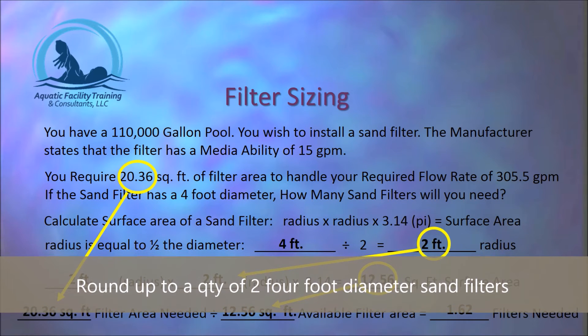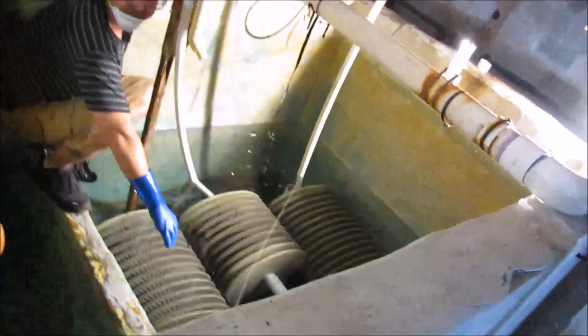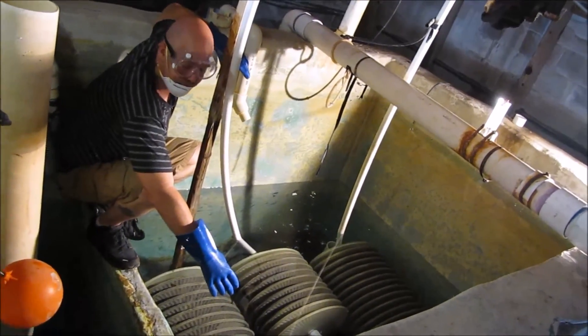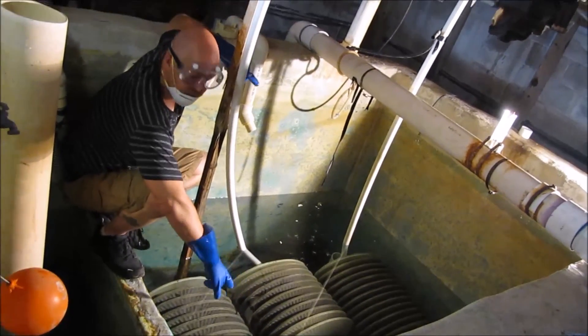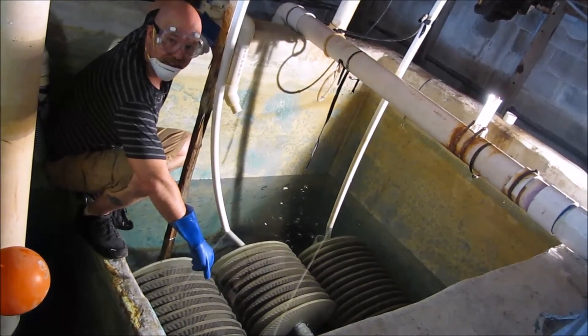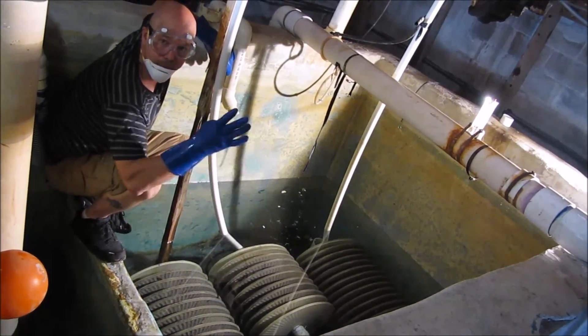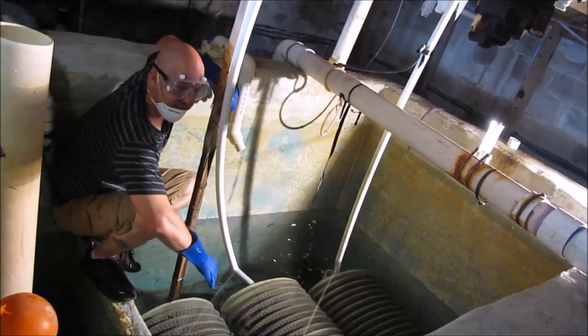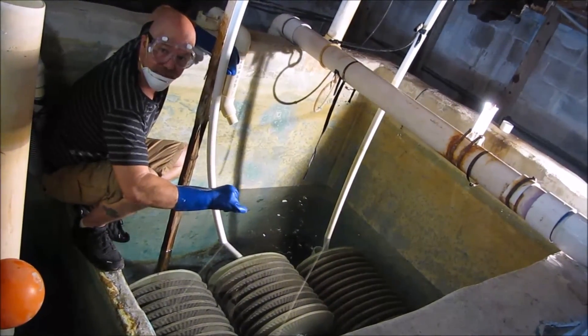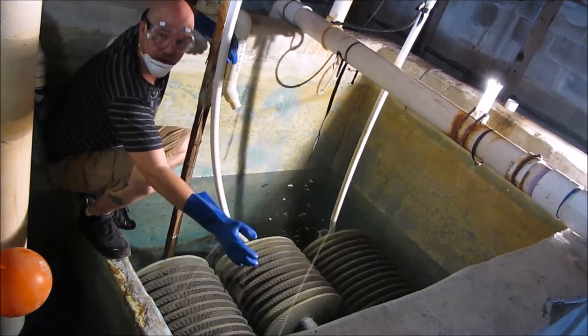The diatomaceous earth in the system coats the outsides of the grids. It's actually the DE that does the filtering — the grids are only there to hold the diatomaceous earth in place. Diatomaceous earth can pull particles from the water down to 4 microns in size. The human blood cell is about 8 microns across, which gives you an idea of the size of particle this system can actually remove from the water.